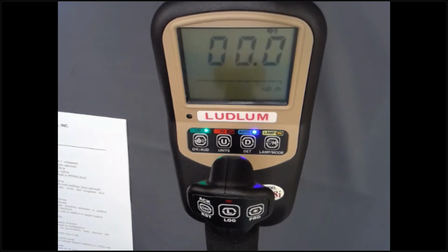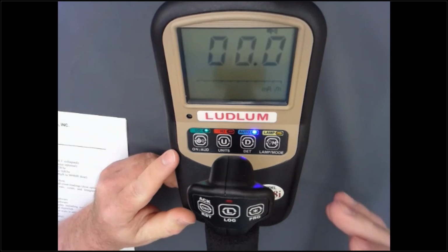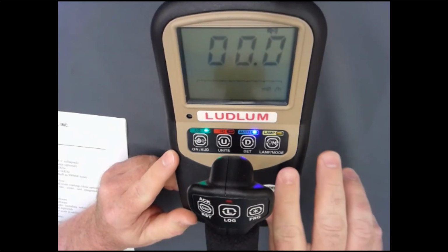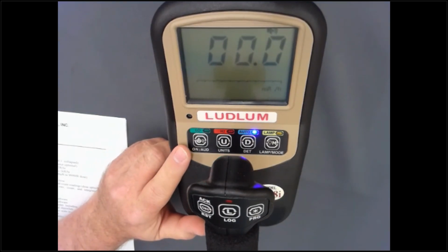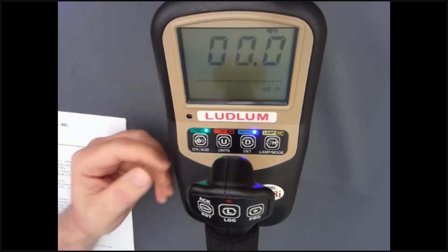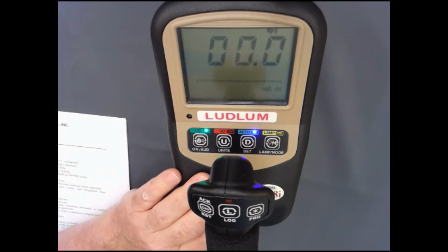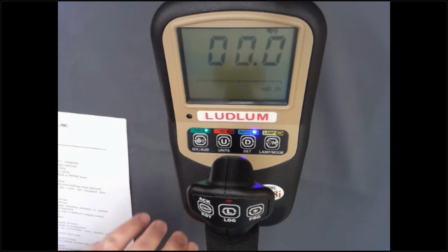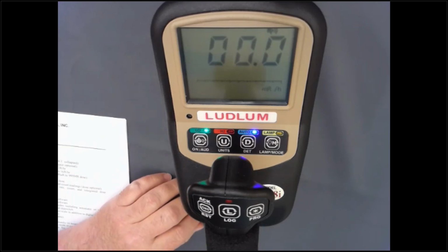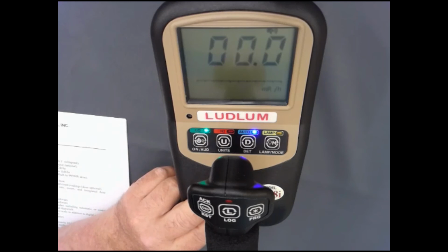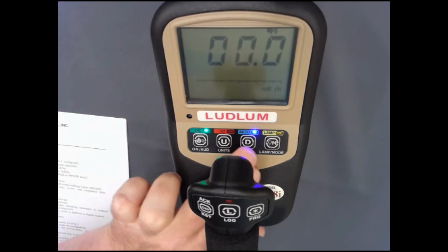Let me switch over and I'll show you some of the features of the instrument from the keypad standpoint. The instrument comes with 7 buttons on the instrument, 4 main buttons, as well as 3 buttons on the handle. The primary button, of course, is the on button. You press and hold it for approximately a second, and the instrument will start to power up. Once the instrument powers up, you'll get an indication of the state of the instrument. In this particular case, the blue LED is lit, so we are in auto ranging mode, and the green LED is flashing to indicate that we are currently looking at the low range detector at the end of the scope. If you want to, you can also individually control the detectors on the end of the scope by pressing the detector button.